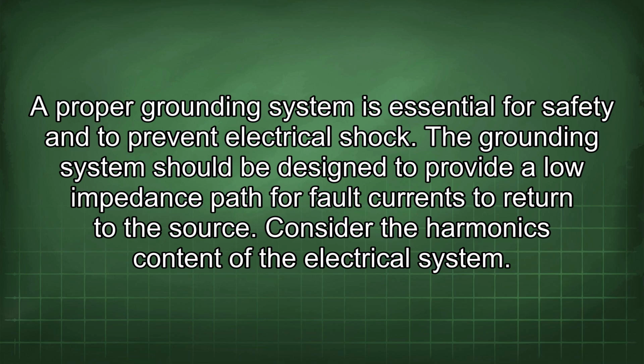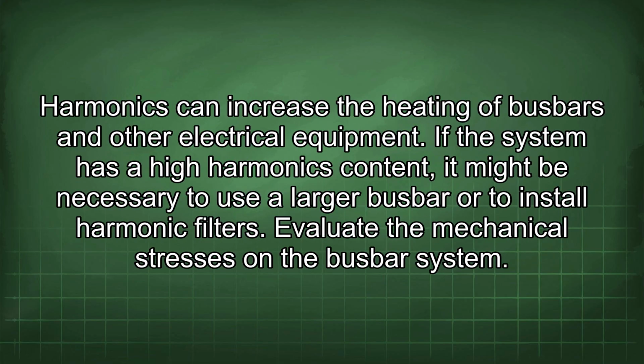Consider the harmonics content of the electrical system. Harmonics can increase the heating of busbars and other electrical equipment. If the system has a high harmonics content, it might be necessary to use a larger busbar or to install harmonic filters. Evaluate the mechanical stresses on the busbar system.